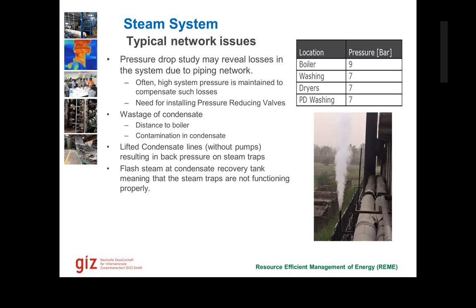And sometimes the condensate lines are lifted. So instead of recovering condensate by gravity, without installing pumps, they install condensate lines on top. So after the steam trap, the line is going towards the roof. That is where the piping is done, the old-fashioned way. And they think that with the pressure of steam, the condensate will be lifted automatically.